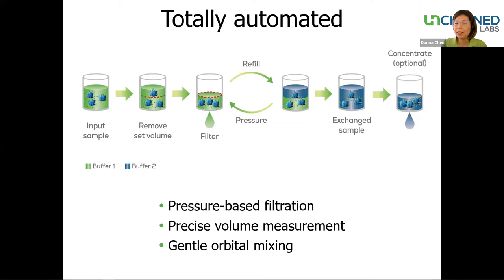At the end of the buffer exchange process, Big Tuna can also concentrate the sample down to your target working concentration range, or it can bypass buffer exchange and go directly to concentration. Throughout the entire buffer exchange process, gentle orbital mixing is occurring simultaneously. This helps fast-track buffer exchange by constantly stirring particles to prevent concentration gradients from building up near the membrane surface, mitigating the risk of clogging the membrane.